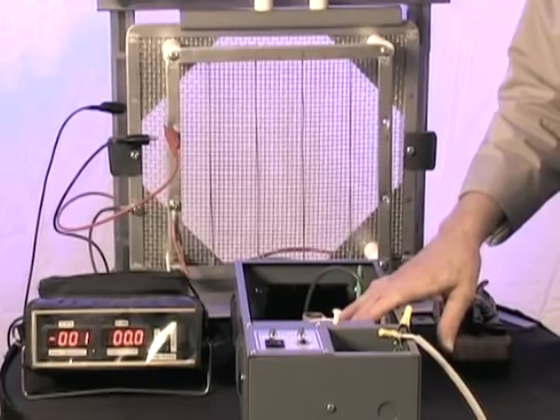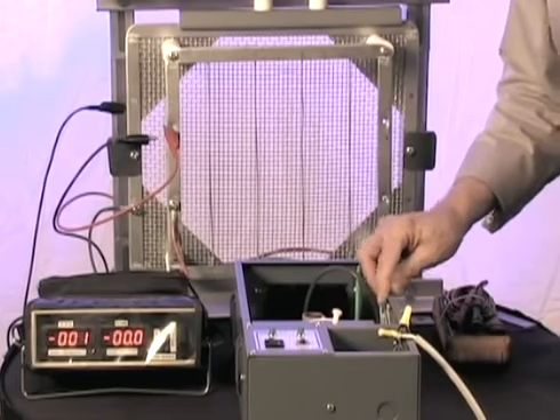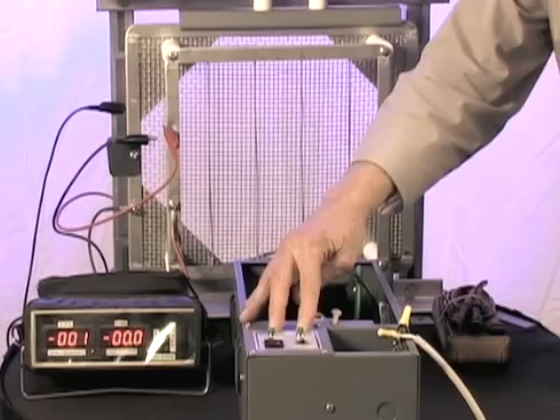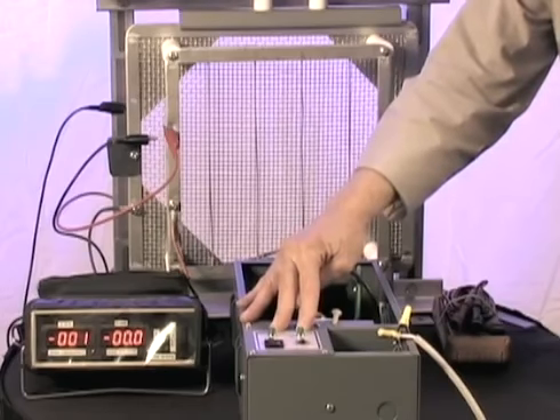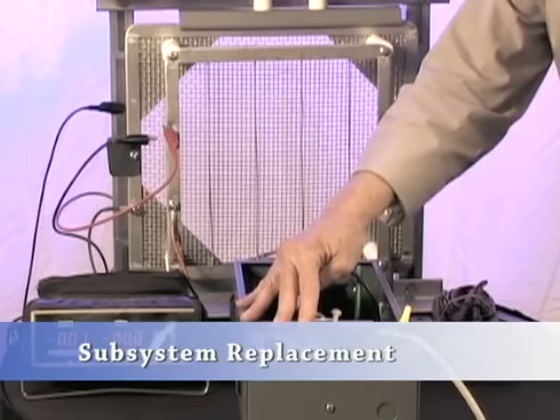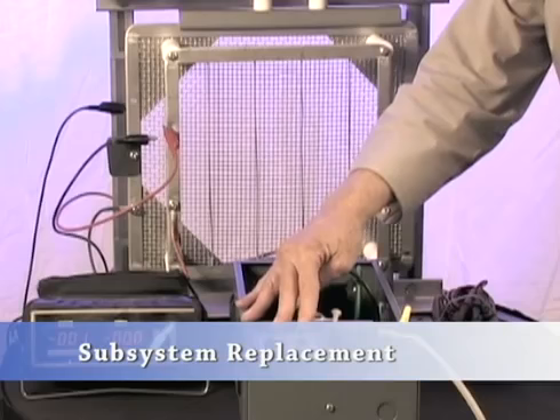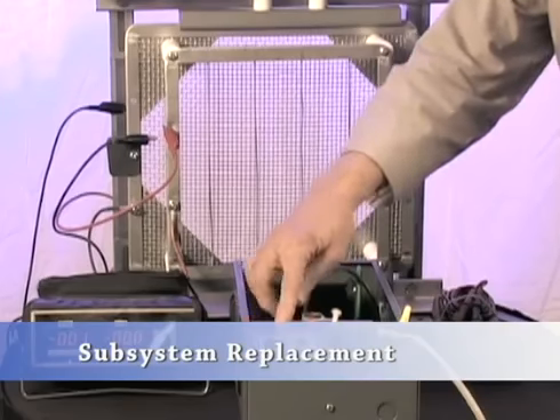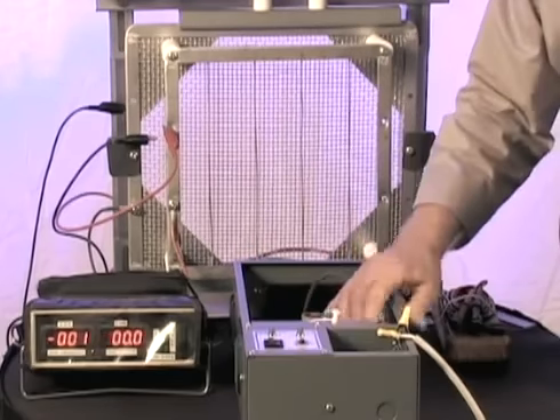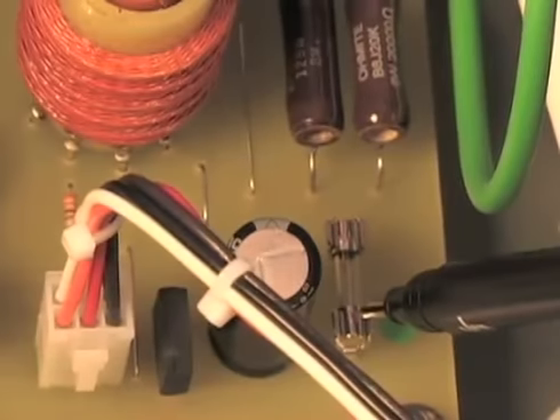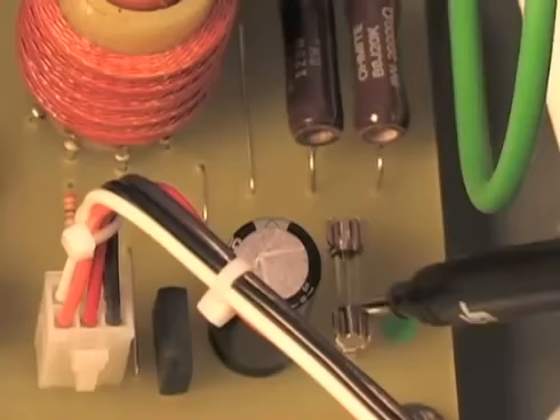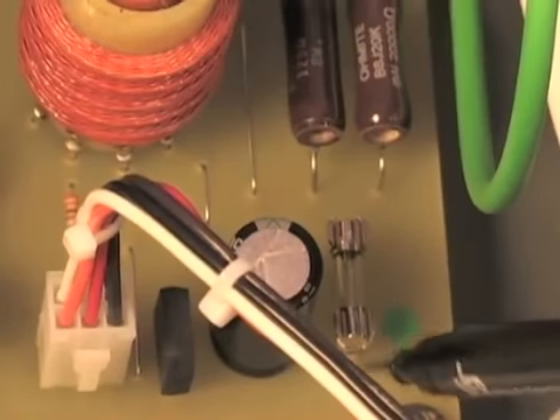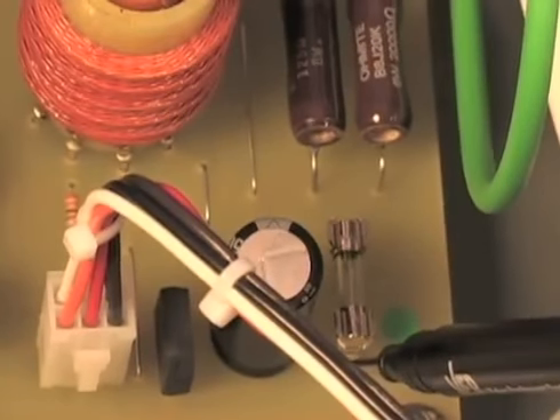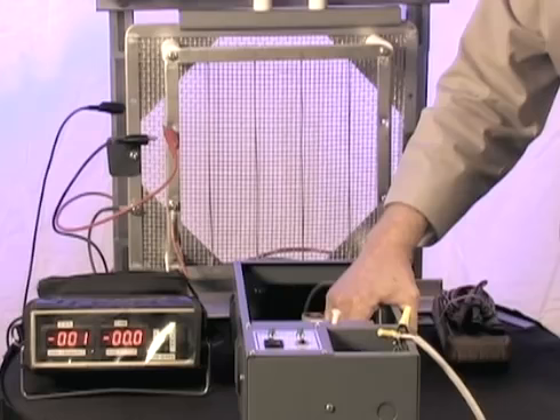If you've come up to your CosaTron system and the HV or the HF light are out, you have a problem with one of the circuits internal to the CU650. The high voltage is serviced by a high voltage module, which is independently fused, and if that fuse blows, then the high voltage module will not function and there will be no high voltage output. And the high voltage module will need to be replaced.